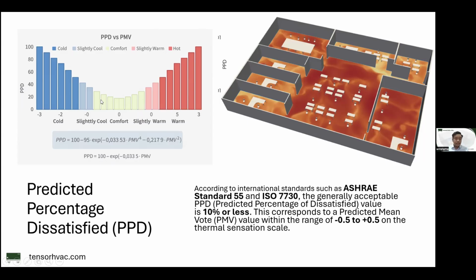This can be calculated from the PMV value by using this simple equation. Not really simple actually, but we can easily calculate how many percent of the occupants will be uncomfortable statistically. And again, the lower the value the better. Then ASHRAE 55 suggests we use this 10% value. Again, the values of PMV and PPD, 0.5 and 10%, are based on the latest standard, but you have to check if there is any update in that standard. So maybe these values can change over time, but the idea is still the same. Okay, this is PMV and PPD.